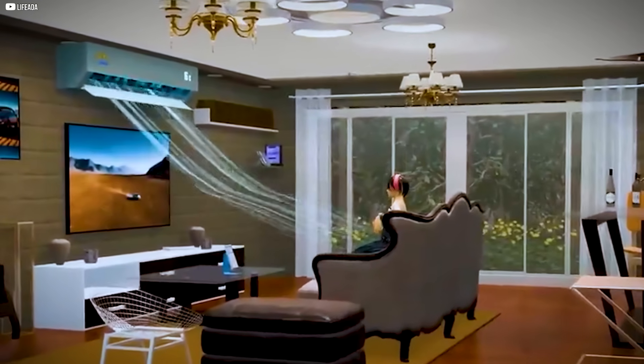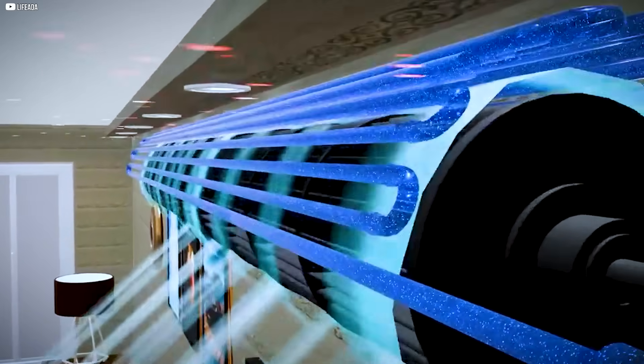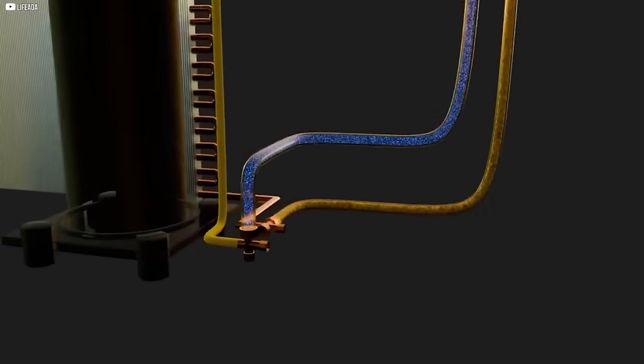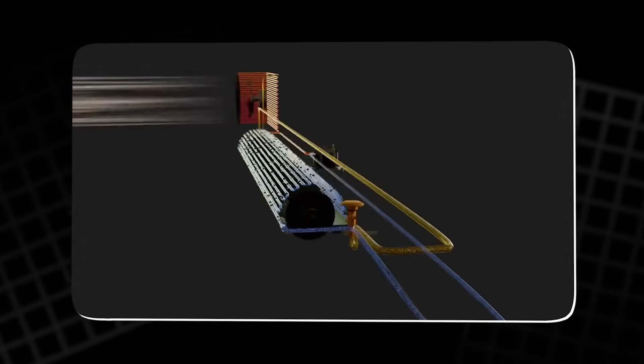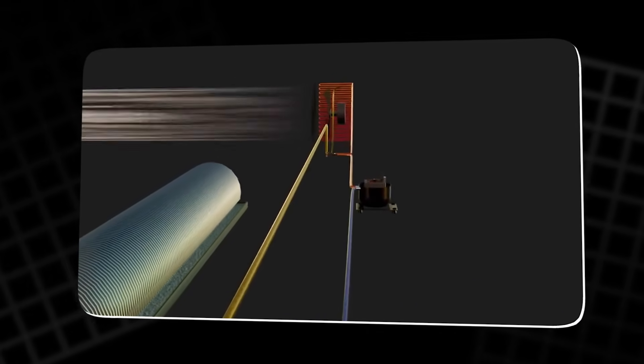The efficiency of a heat pump is measured by its coefficient of performance, COP, which tells you how much heat the system delivers compared to the electricity it consumes. For example, a COP of three means the pump provides three times as much heat as the electricity it uses.